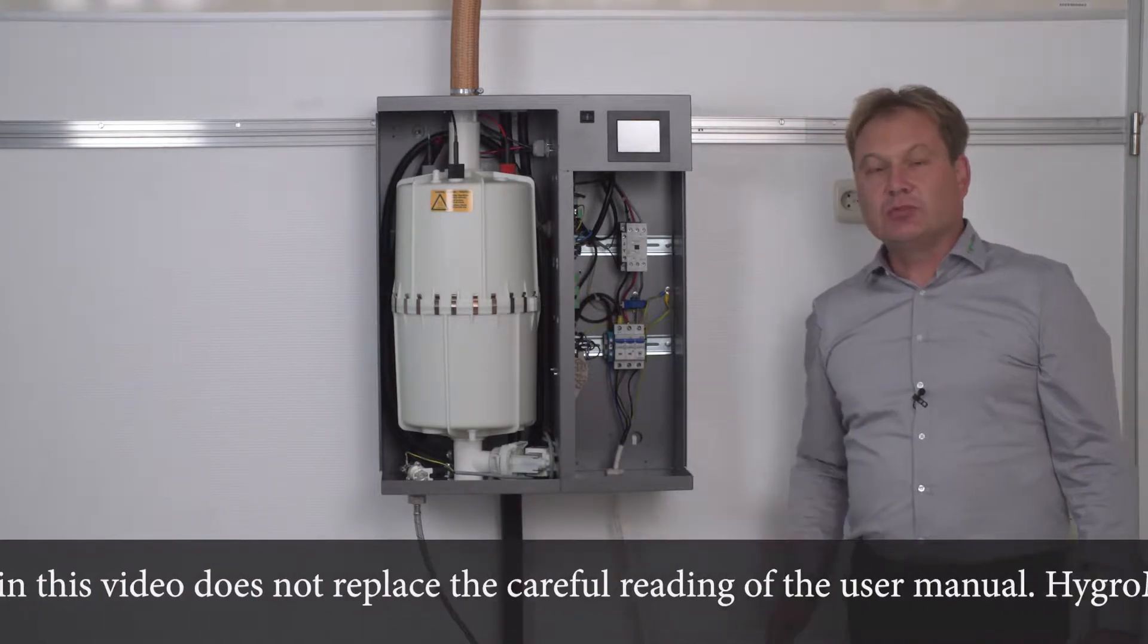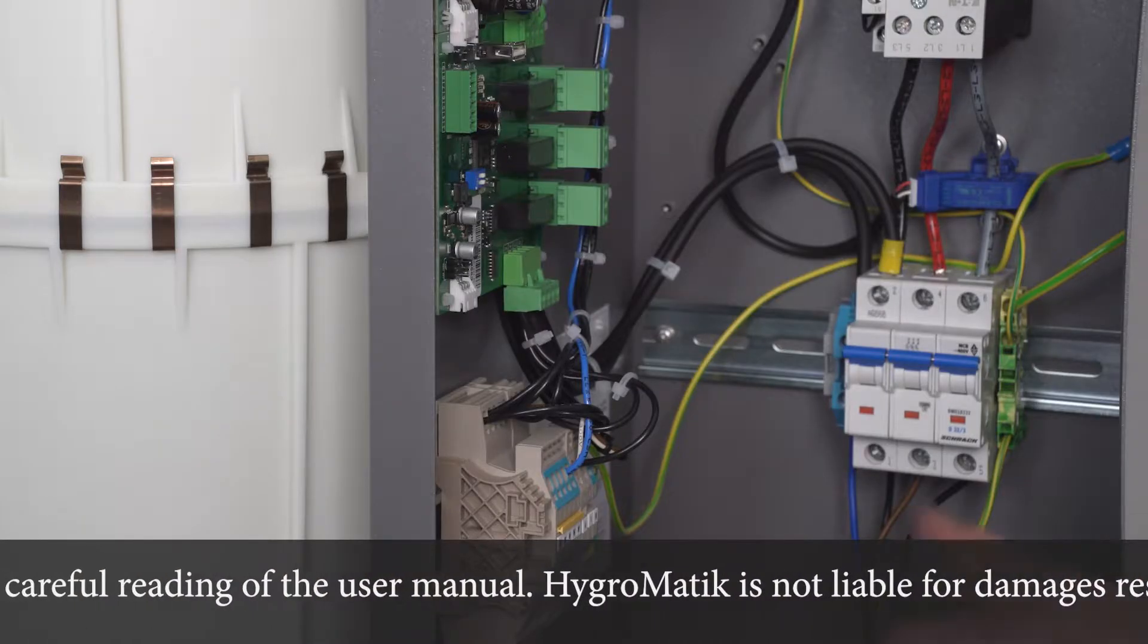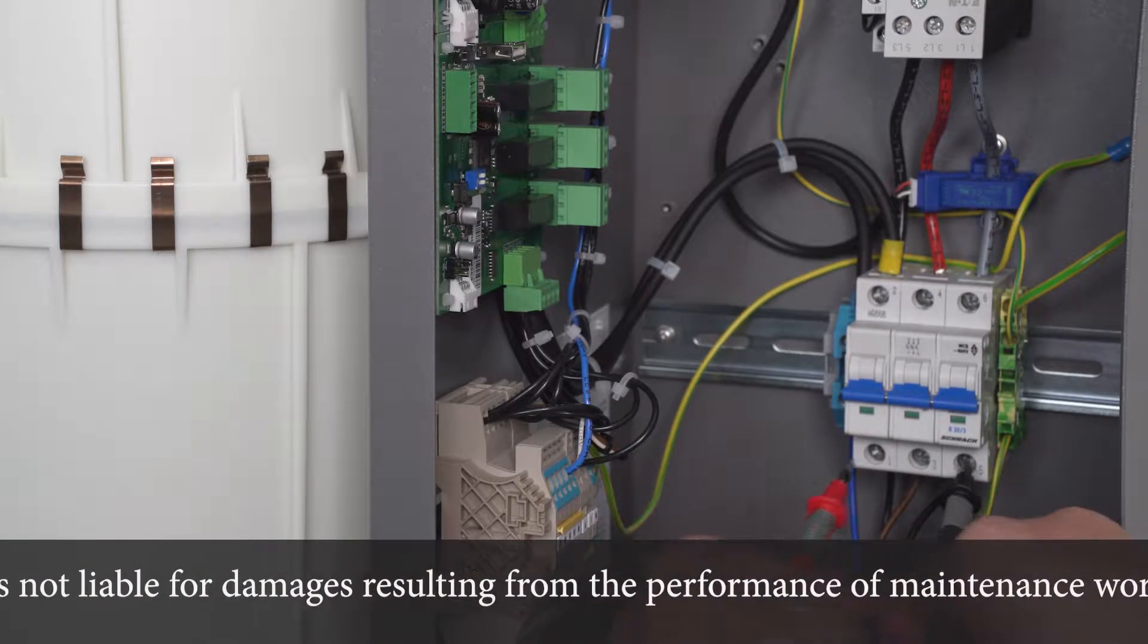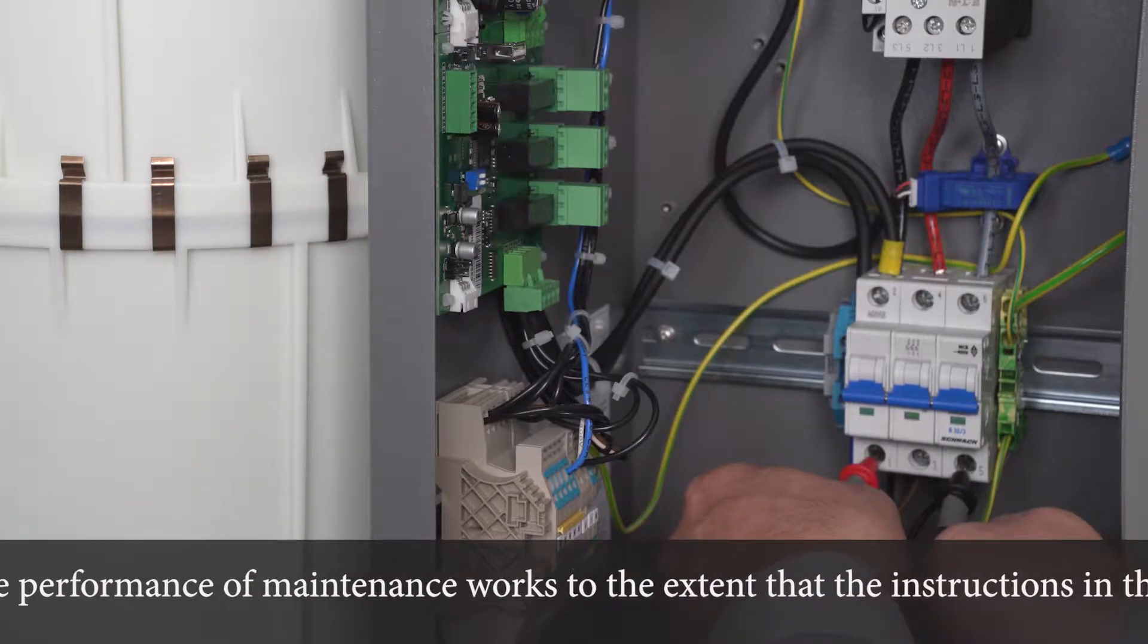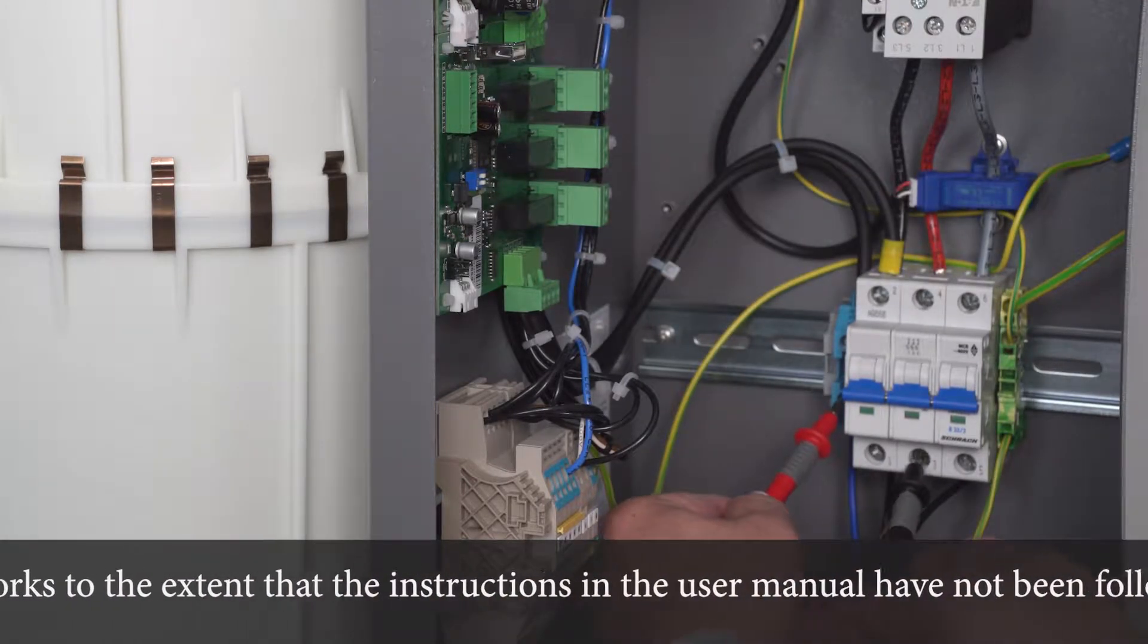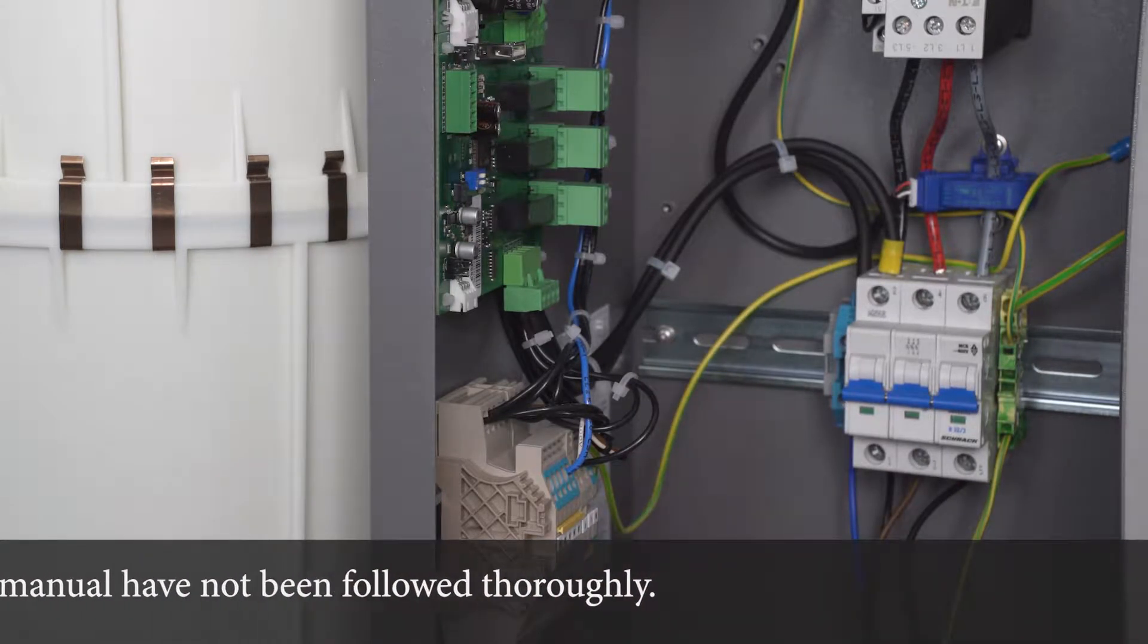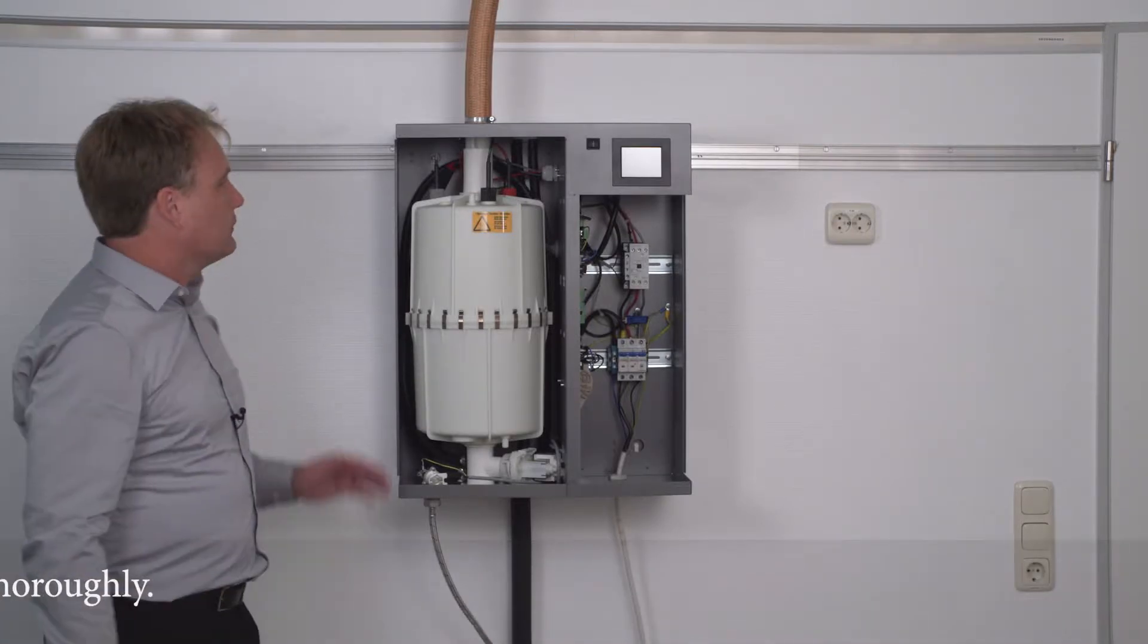Before I can start with the actual maintenance work I have to make sure that the power is off. To do this I check the circuit breaker that I switched off before. I first check for any phase to phase voltage and afterward I check for phase to neutral voltage. There is no voltage present. After I have checked for absence of power I can safely disassemble the steam cylinder.